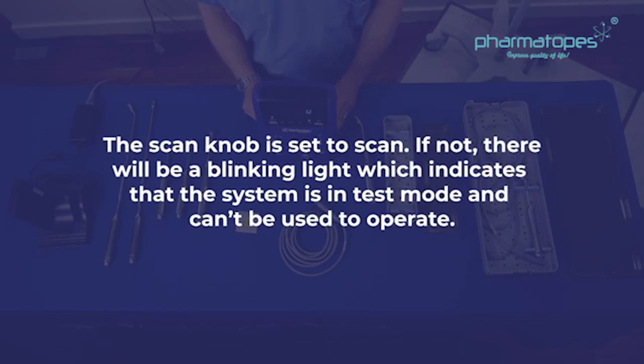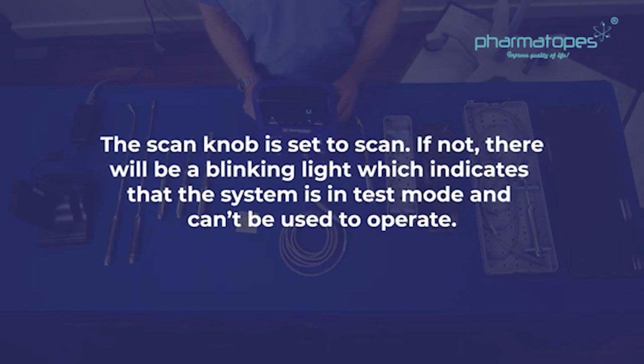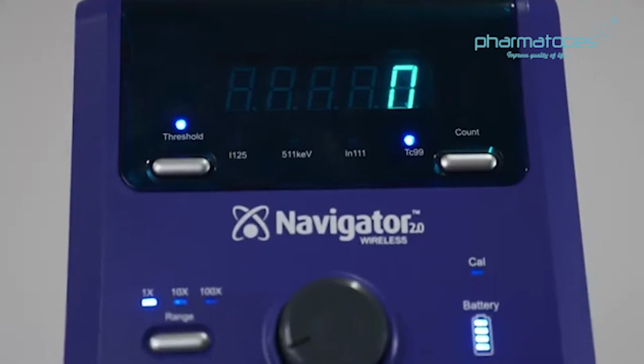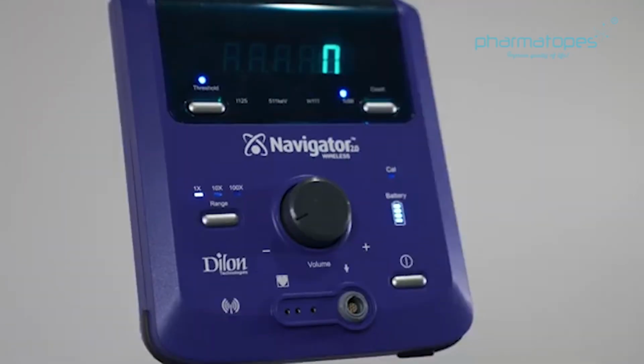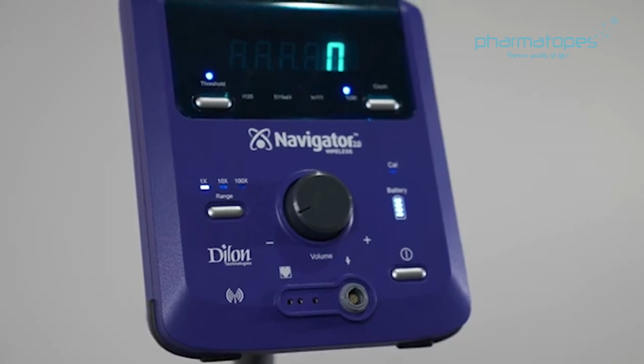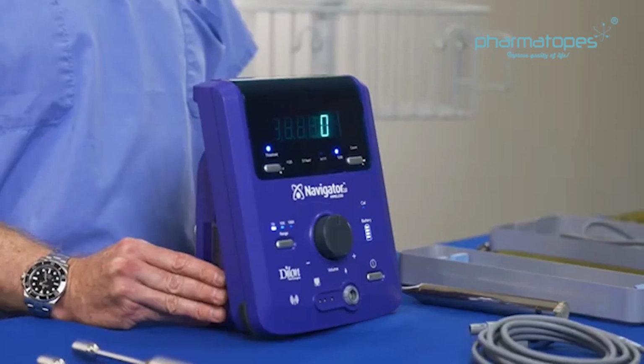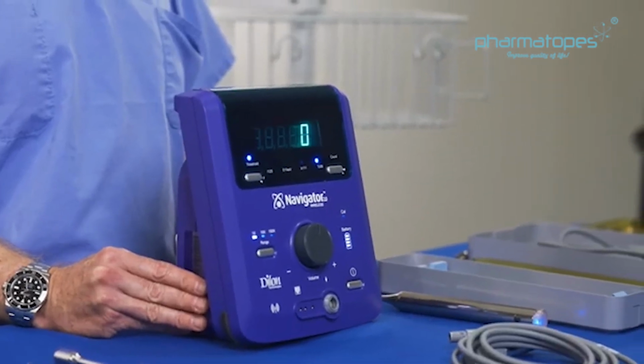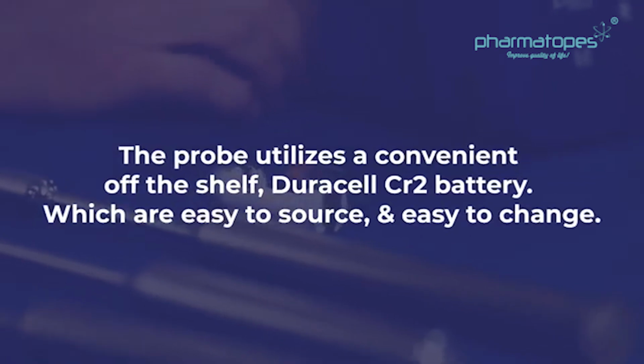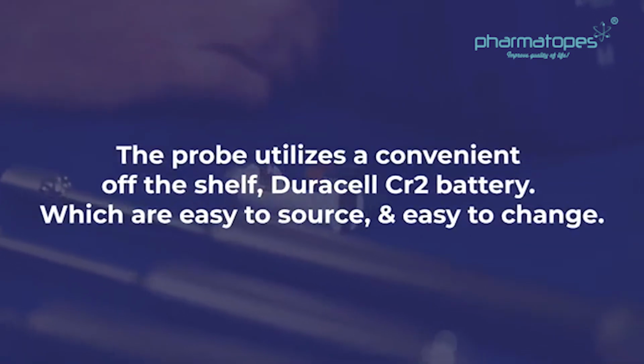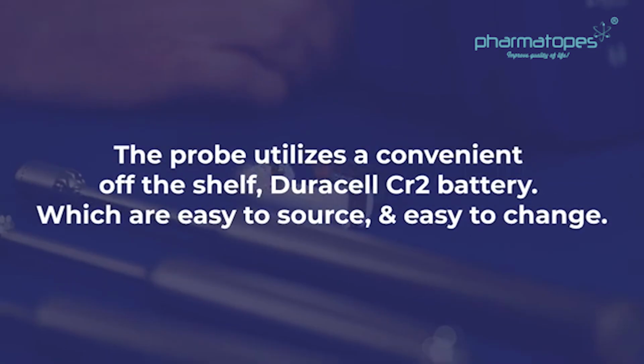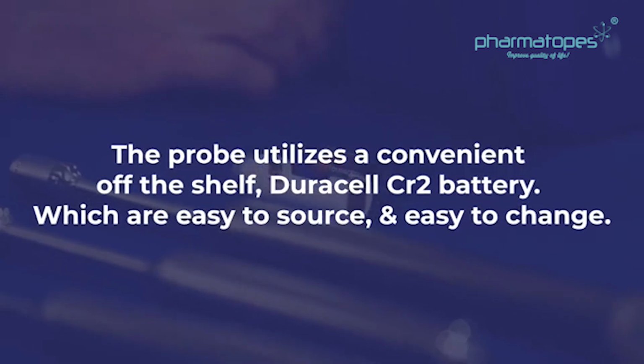If not, there will be a blinking light which indicates that the system is in test mode and can't be used to operate. The threshold light is on and the range is on 1x, and you are set to the desired radiation source. When turned on, the display will read 0. The probe utilizes a convenient off-the-shelf Duracell CR2 battery, which are easy to source and easy to change.